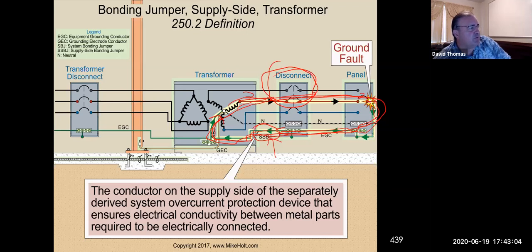But what I had to do is install ground fault detectors, or a system to protect and shut the breaker off, or make an alarm. In this case, it was actually an alarm. If one of the wires had touched the ground, we didn't want to trip the breaker. We wanted to just let everybody know by a horn that we have a ground fault, and it would just blare this horn out, so everybody knew, oh, we've got a problem. And at that point, they can turn the motor off in sequence.